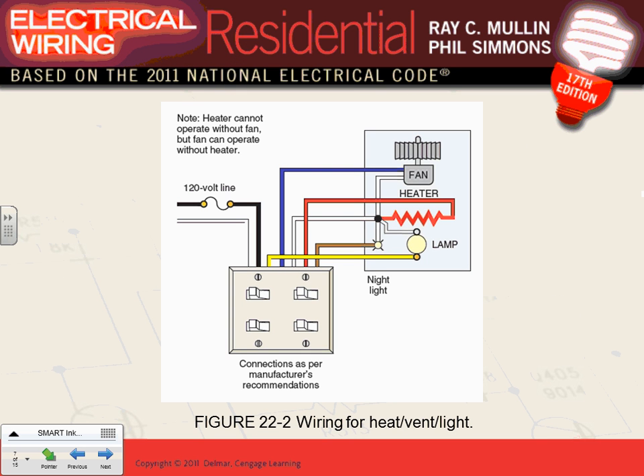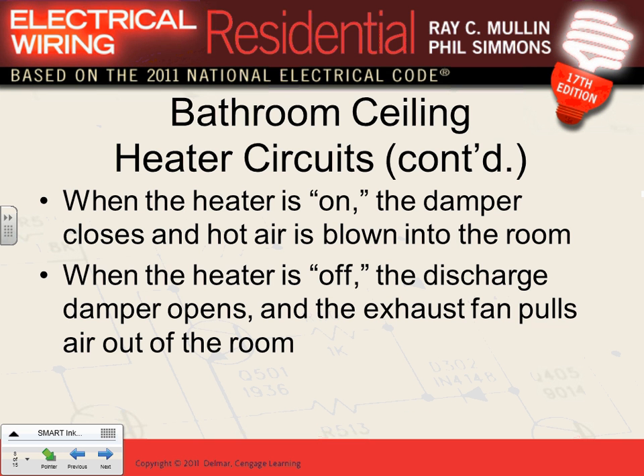I can't emphasize, look at this here. It says per manufacturer recommendations. That's directly from the manufacturer. 20 amp circuit, switch them this way. Could I have put all of them on a 20 amp circuit, with a 20 amp snap switch? Yes. Would it be a good idea? No, because you can start the heater in the summer.